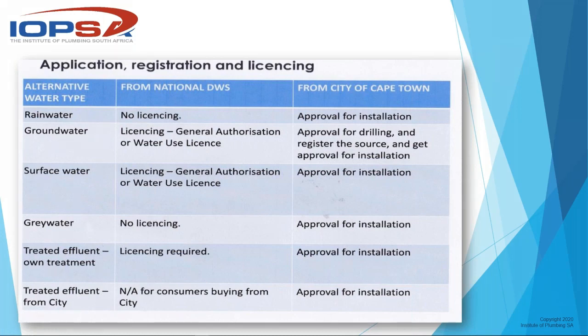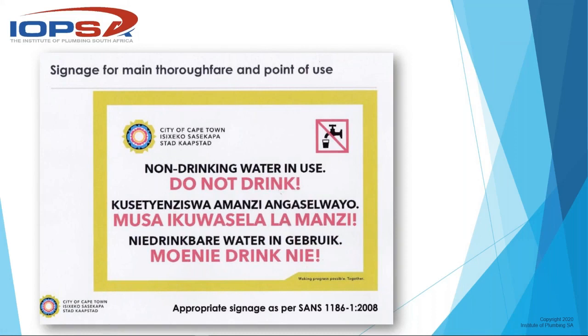It's not just about putting an RPZ valve in — there is also signage that must be put up. There must be signage on all main thoroughfares and points of use. So if you've got a tap on a rainwater system, you have to have a sign that says 'non-drinking water in use — do not drink' in your three main languages: English, Afrikaans, and an African language. Nobody can accidentally drink contaminated water, so you must make sure it is well signposted.